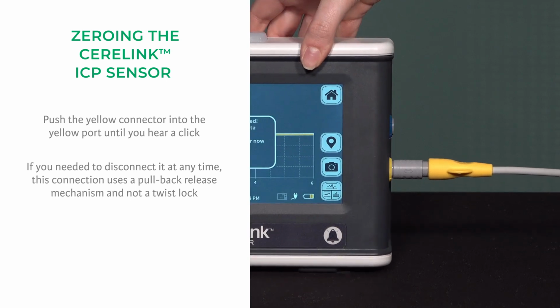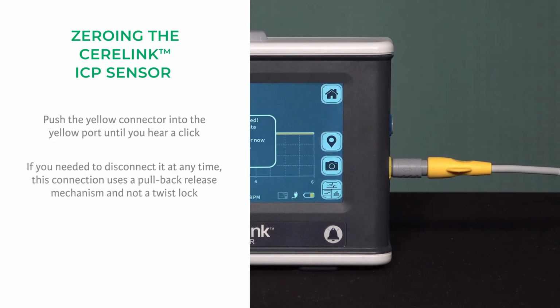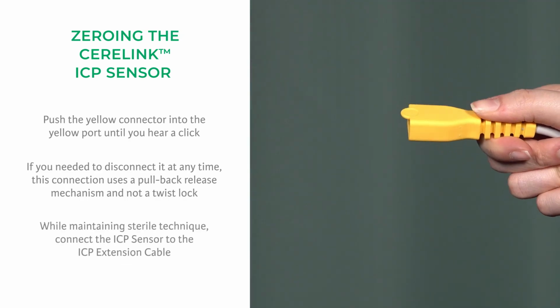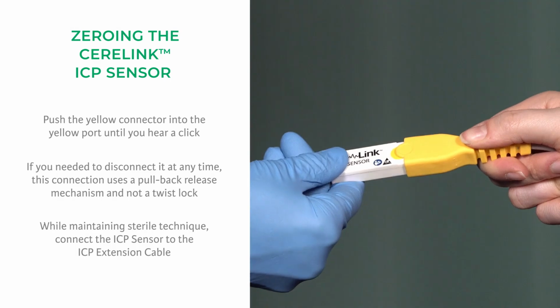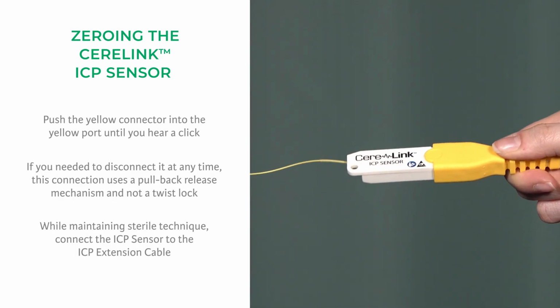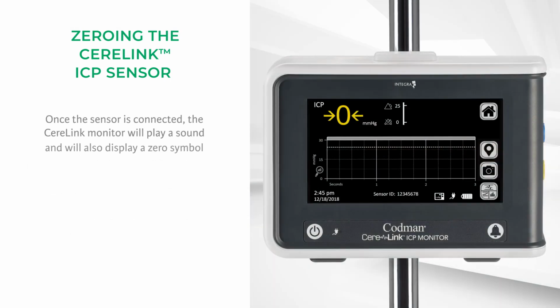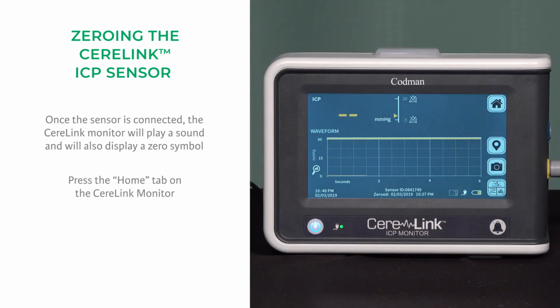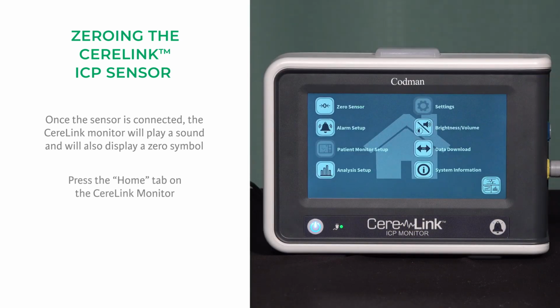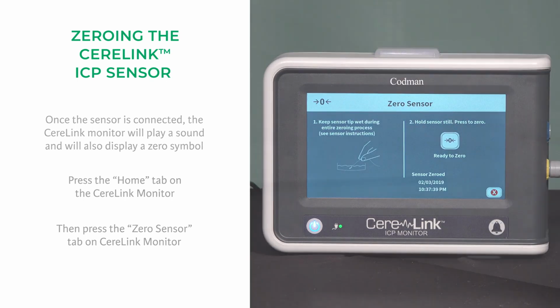If you need to disconnect it at any time, this connection uses a pullback release mechanism and not a twist lock. While maintaining sterile technique, connect the ICP sensor to the ICP extension cable. Once the sensor is connected, the CereLink monitor will play a sound and will also display a 0 symbol. Press the Home tab on the CereLink monitor. Then press the Zero Sensor tab on the CereLink monitor.